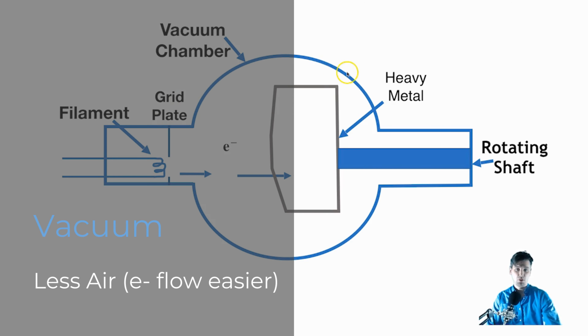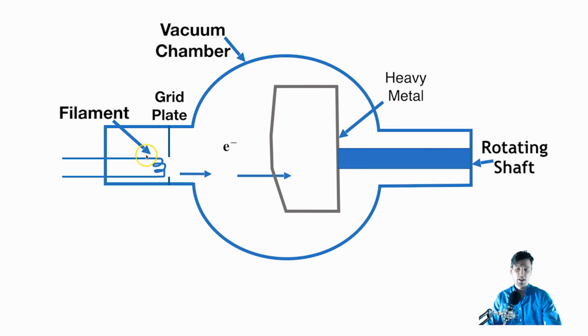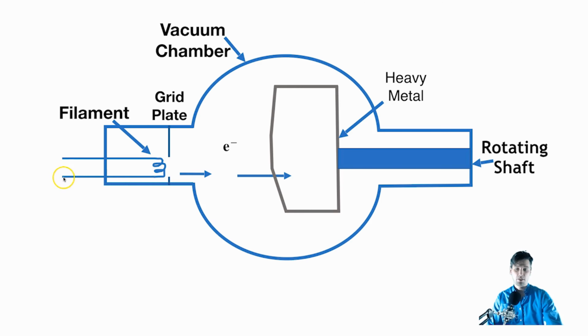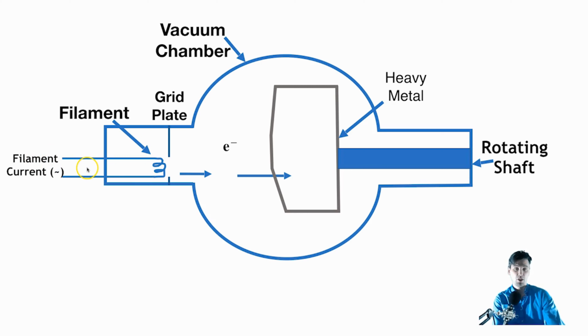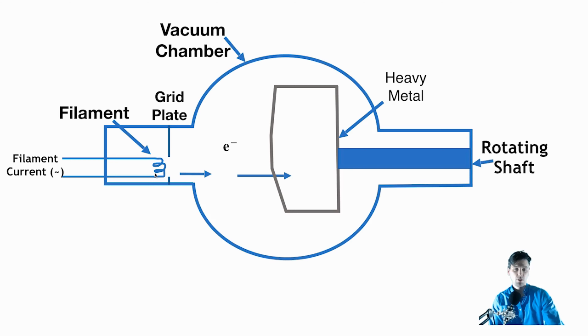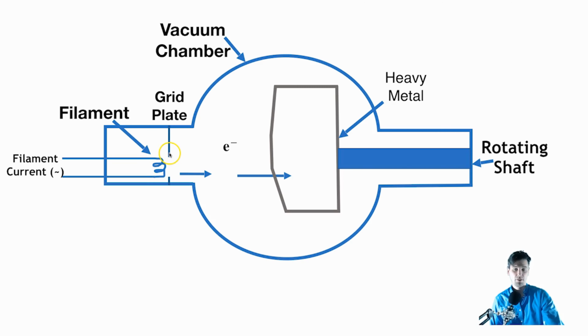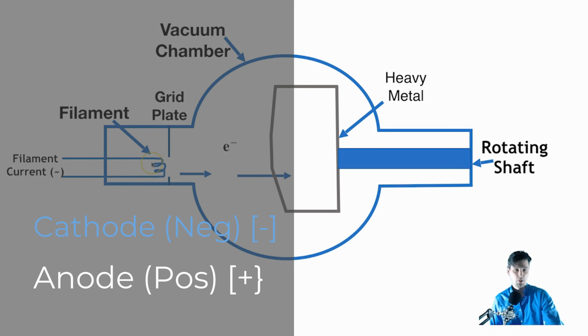Here's a schematic where you have a vacuum tube. On the inside there's a relatively good vacuum. We have a filament here, and this is going to be the source of our electrons. A current goes across this filament, and that filament current is used to heat it. The way that we generate electrons is by heating this filament and essentially boiling off those electrons. Those electrons are negatively charged, so we establish a potential — a reason why the electrons want to move. We need a relatively negative charge at what we call the grid plate, and a positive charge at the anode.